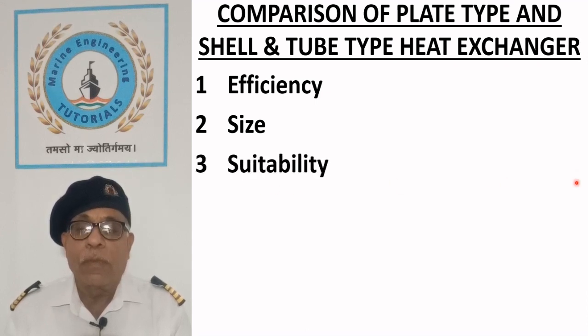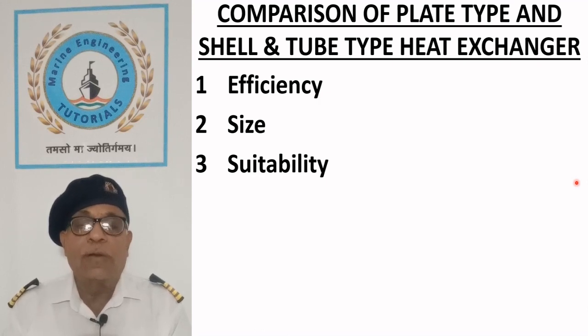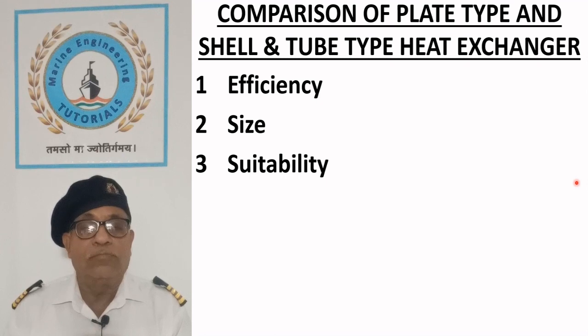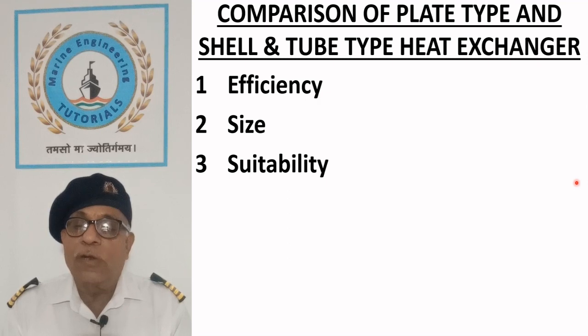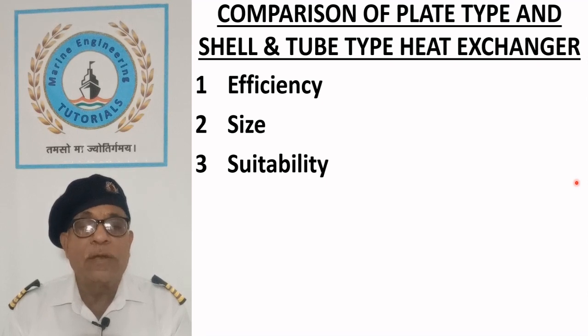Suitability. Plate type heat exchangers are not suitable for pressures above 20 bar and temperatures above 110 degrees centigrade, although shell and tube type heat exchangers are suitable. Plate type heat exchangers are generally used for liquids as in coolers, whereas shell and tube type heat exchangers can be used for both vapors and liquids as in coolers, condensers and heaters.